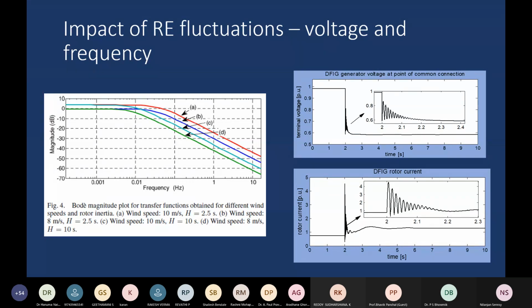So the problem with the doubly fed induction generator is that when the terminal voltage of the generator drops, the rotor current rises. And here you can see in the bottom figure that the rotor current rises by at least 4 times. And this can easily destroy your rotor side converter. So of course, this kind of situation forces you to actually switch off the wind turbine in the event of a low voltage situation in the grid. So such an action can become very costly.